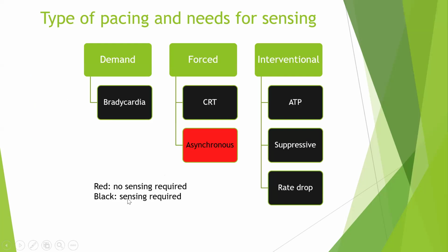And now I go through types of pacemaker, depending on the functionality. Most of the pacemakers do what we call demand pacing. Demand pacing means that the pacemaker will only pace if the patient needs pacing. So this is primarily for bradyarrhythmia, sinus arrhythmia, sick sinus syndrome, or AV node disease like 2-to-1 block or complete heart block. So the demand pacing is basically to treat bradyarrhythmia, and it requires sensing, because without sensing, it will not know if the heart rate is slow or fast.